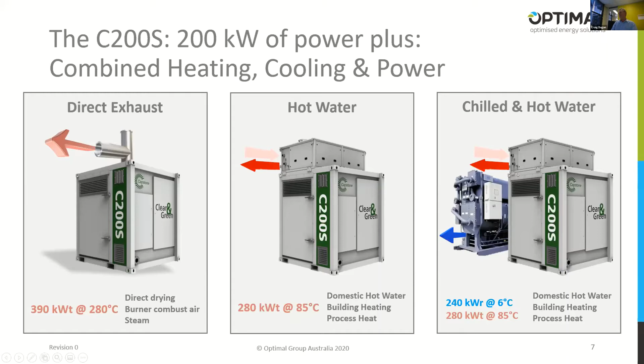Because there's no lube oil systems or cooling water systems, all of our waste heat is in the exhaust. You can see here that's at 292 degrees, so we can do direct heating with that. We can do hot water, or hot water to chilled water, or steam.